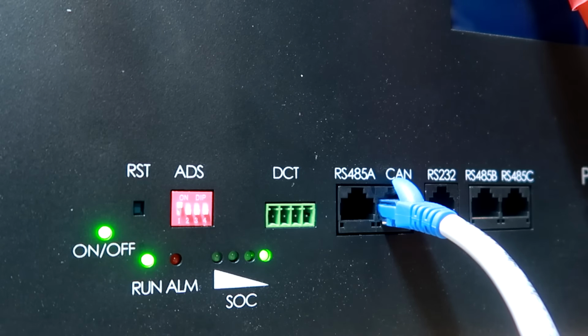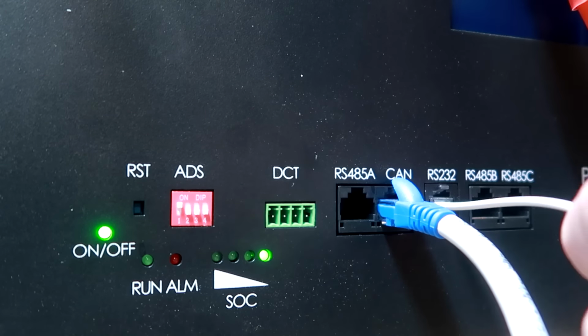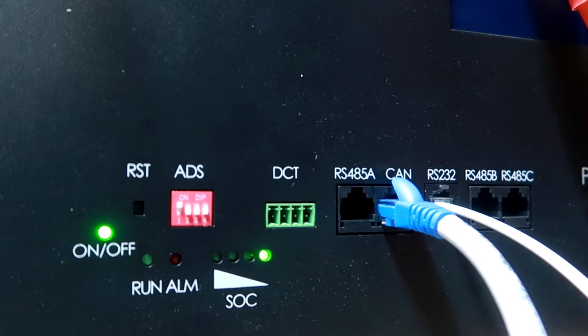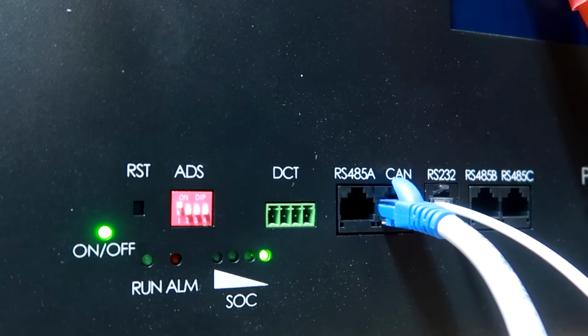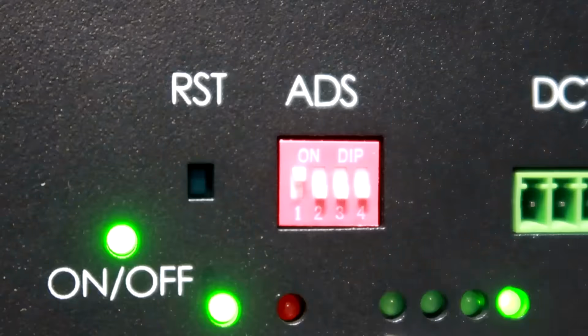And then we have our RJ11 communication cable, RS232, which goes to our computer via an adapter. And then we have to program the master and the slave batteries with these dip switches. So if you have a single battery or a master battery, you have to put dip switch number 1 to on in the upper position, and all the other 3 dip switches are in the off position. We have just set the master to battery number 1, and now we have to set the slave battery to number 2.